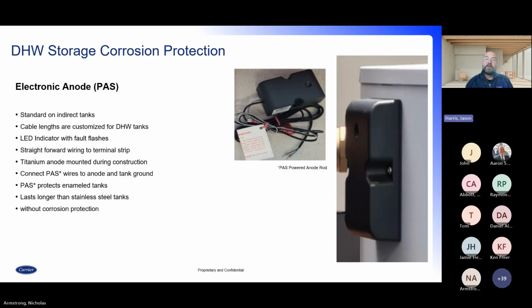Corrosion protection: it comes with a powered anode system. The powered anode is a titanium anode. The manufacturer says it has better corrosion protection than stainless steel tanks that do not have corrosion protection. So with the anode and the tank, it should last for a very long time and outlast stainless steel tanks. And the wiring for the anode is straightforward, so you can't mess that up.